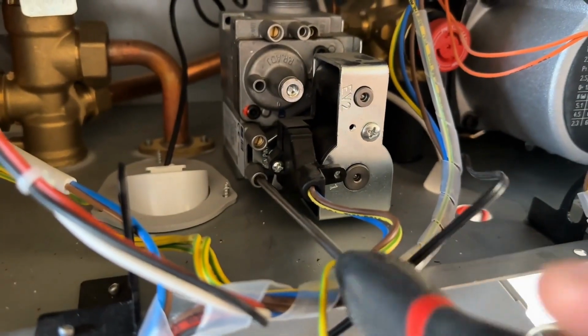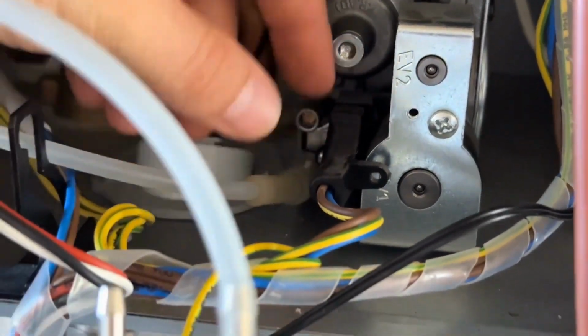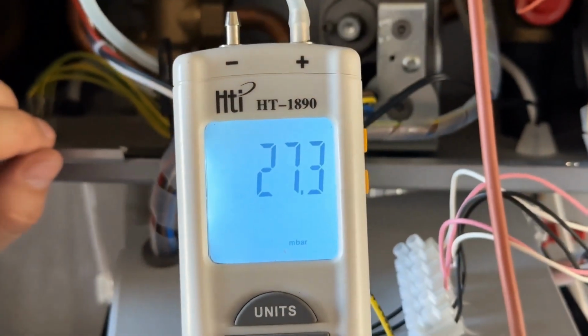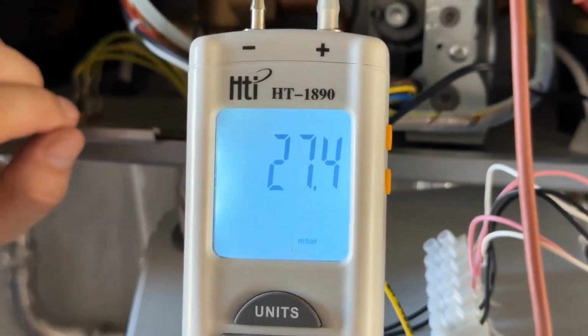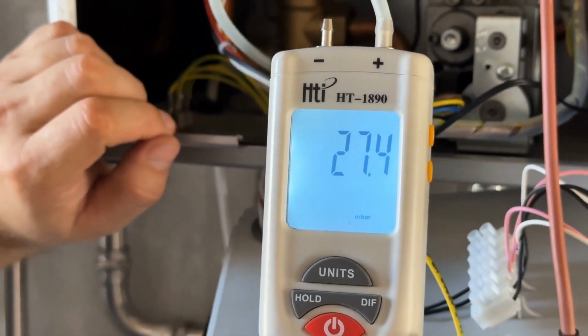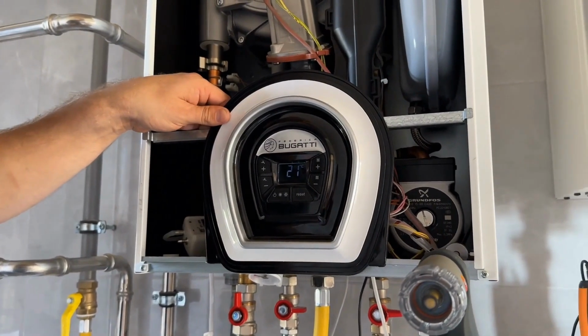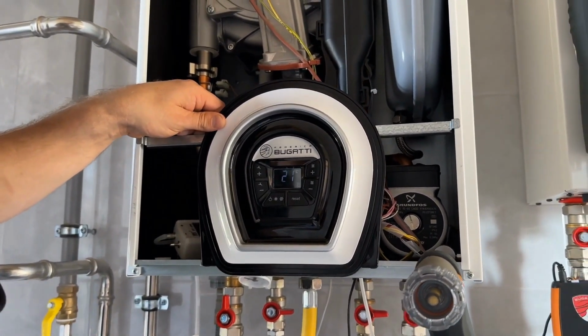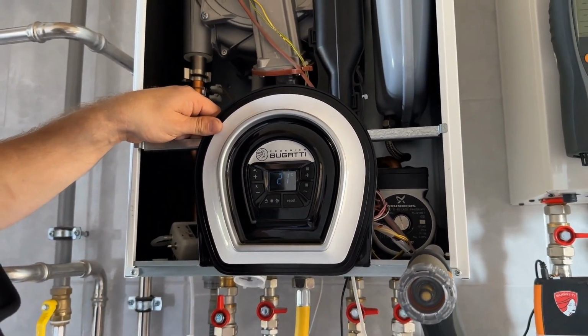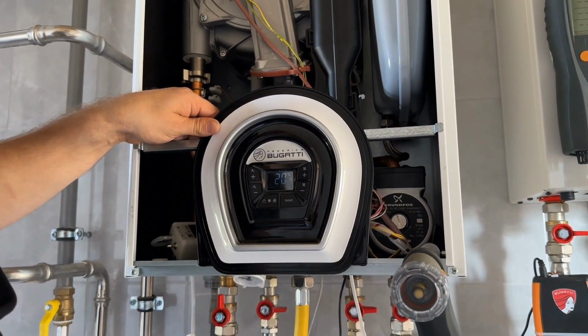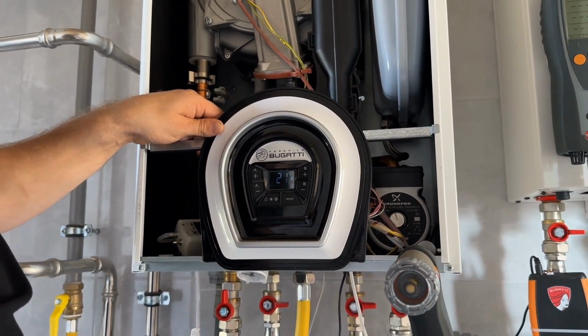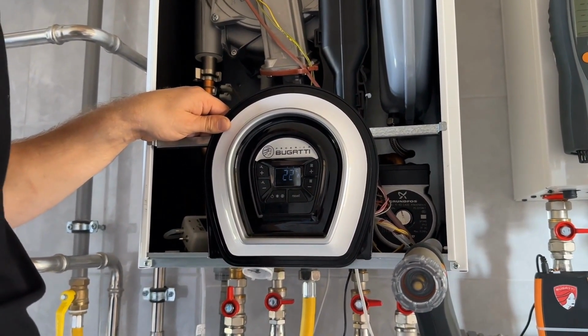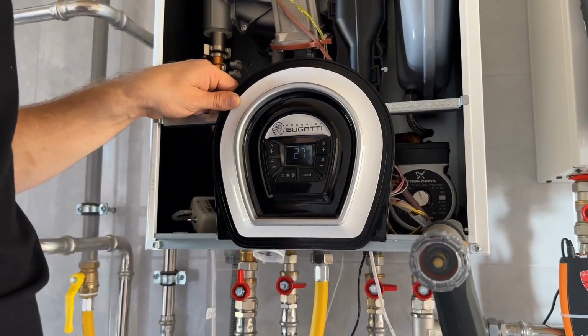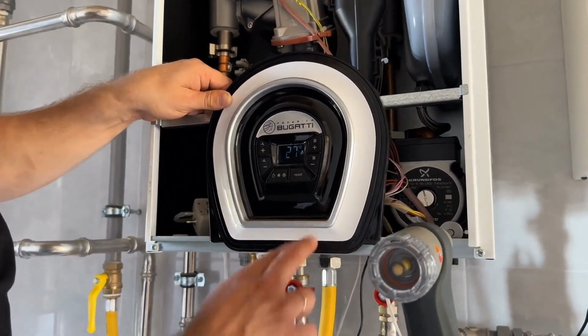We loosen the lower fitting, connect the micromanometer, and measure the pressure. For the normal operation of the boiler, the static pressure must be at least 15 millibars. After resetting the error, we start the boiler with the gas valve open. We listen carefully to how the ignition occurs. The ignition happens smoothly and steadily. The flame burns steadily. We proceed to measure the exhaust gases from the condensing boiler.